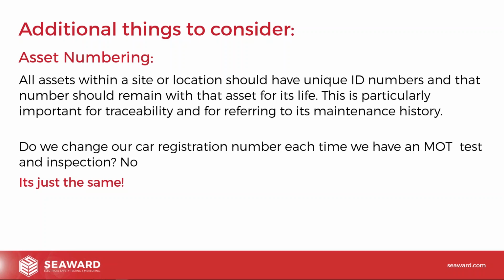Keep the same asset number all the way through, and that really gives you the traceability you need for a maintenance history. Because if anything does go wrong, what you need to be able to show is that you've been maintaining it in a safe condition, and checking it year on year. Keeping the history also enables you to inform your risk assessment. If you can see the records for the last 10 years, and the item has been absolutely fine every year, then you can feed that into your risk assessment. You can say, well, why are we doing it every year? Let's check it after 2 years and see. So you can use that history to inform your test process.